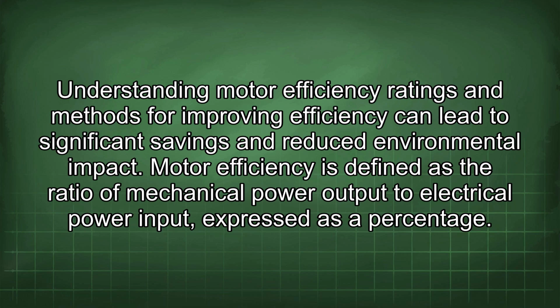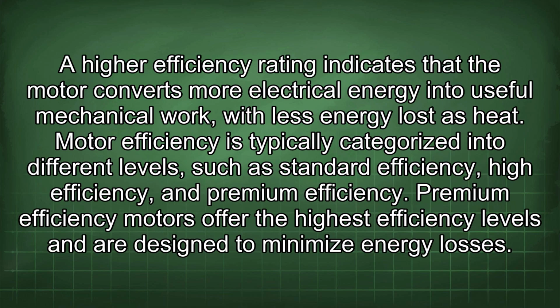Motor efficiency is defined as the ratio of mechanical power output to electrical power input, expressed as a percentage. A higher efficiency rating indicates that the motor converts more electrical energy into useful mechanical work with less energy lost as heat. Motor efficiency is typically categorized into different levels such as standard efficiency, high efficiency, and premium efficiency. Premium efficiency motors offer the highest efficiency levels and are designed to minimize energy losses.